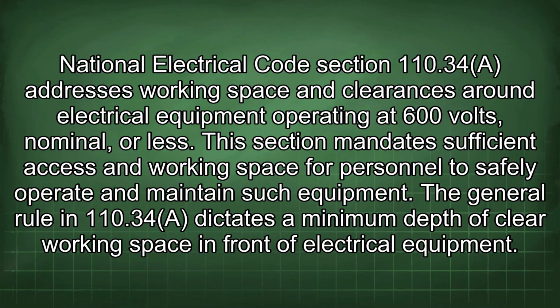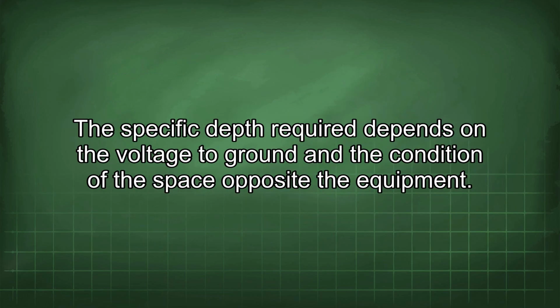National Electrical Code Section 110.34 addresses working space and clearances around electrical equipment operating at 600 volts, nominal or less. This section mandates sufficient access and working space for personnel to safely operate and maintain such equipment. The general rule in 110.34 dictates a minimum depth of clear working space in front of electrical equipment. The specific depth required depends on the voltage to ground and the condition of the space opposite the equipment.